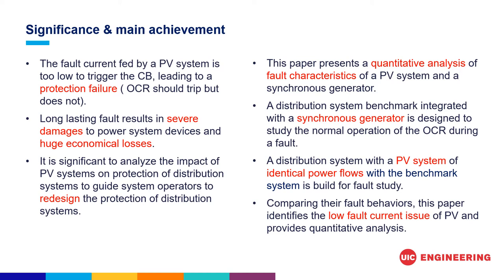To analyze this issue, this paper presents a quantitative analysis of fault characteristics of a PV system and a synchronous generator. A distribution system benchmark integrated with a synchronous generator is designed to study the normal operation of the overcurrent relay during the fault. We also build a distribution system with a PV system of identical power flows for fault study. Comparing their fault behaviors, this paper identifies the low fault current issue of PV and provides quantitative analysis.